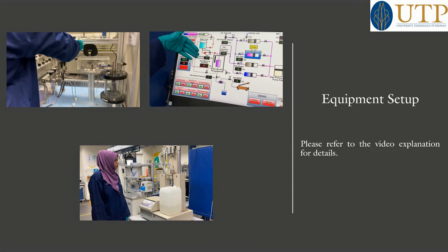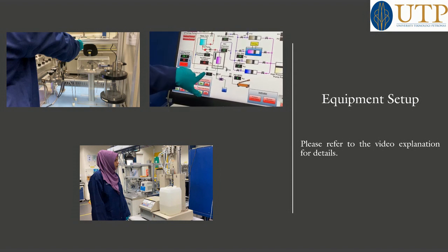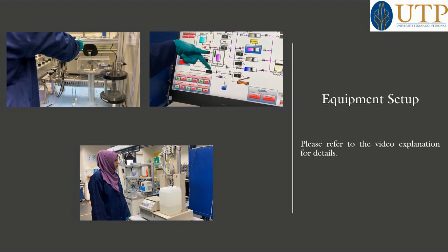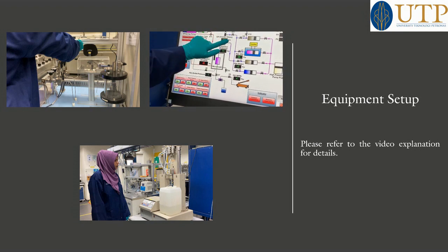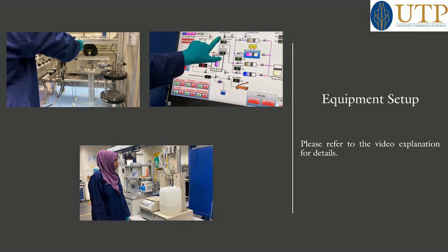Then for our injection pressure and our outlet pressure, you can see here we have a difference between these two. How much? It's almost 10. So this is the difference between our inlet and outlet, the DP. This is the pressure inside our glass.